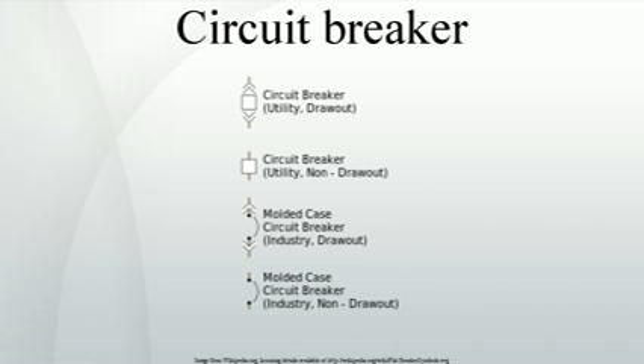Standard current ratings. Circuit breakers are manufactured in standard sizes, using a system of preferred numbers to cover a range of ratings. Miniature circuit breakers have a fixed trip setting. Changing the operating current value requires changing the whole circuit breaker. Larger circuit breakers can have adjustable trip settings, allowing standardized elements to be applied but with a setting intended to improve protection. For example, a circuit breaker with a 400 ampere frame size might have its overcurrent detection set to operate at only 300 amperes, to protect a feeder cable.